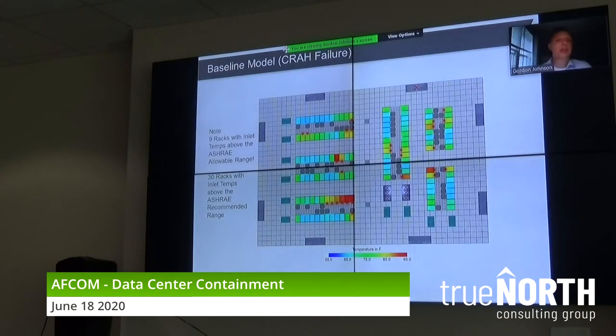What happens when a CRAH fails? Well, if you look in the upper right hand corner where that CRAH has an X, I've turned that off, either it failed or I did some maintenance. Notice how much hotter my data center is. Instead of 14 racks, I have 30 racks that have inlet temperatures above ASHRAE's recommended range. I have 9 racks outside of their allowable range. I'm in a lot of trouble in this data center right now.